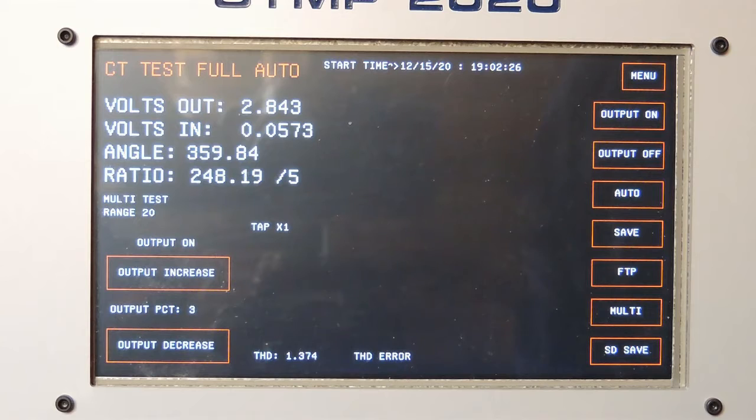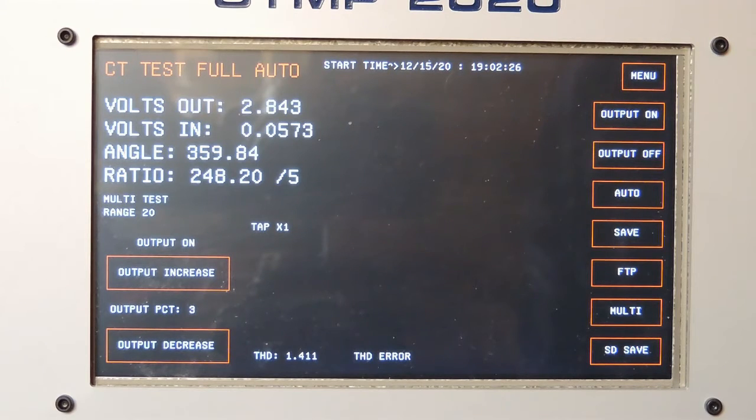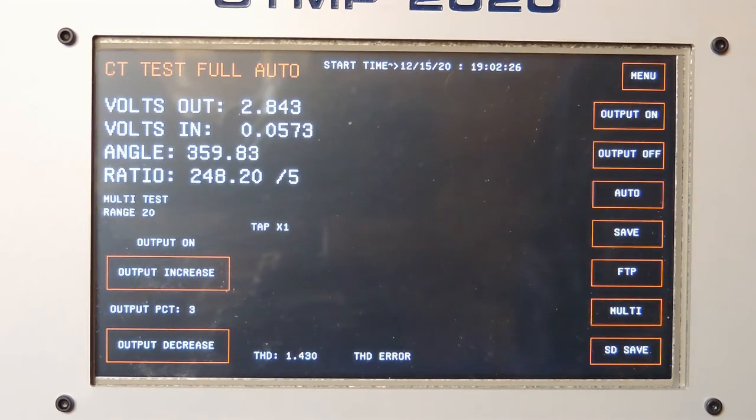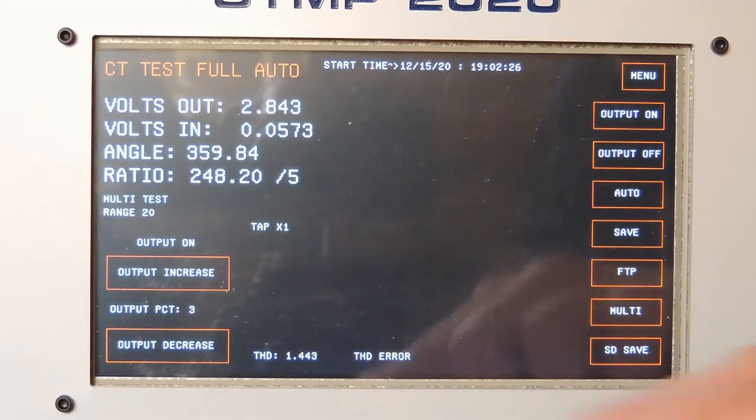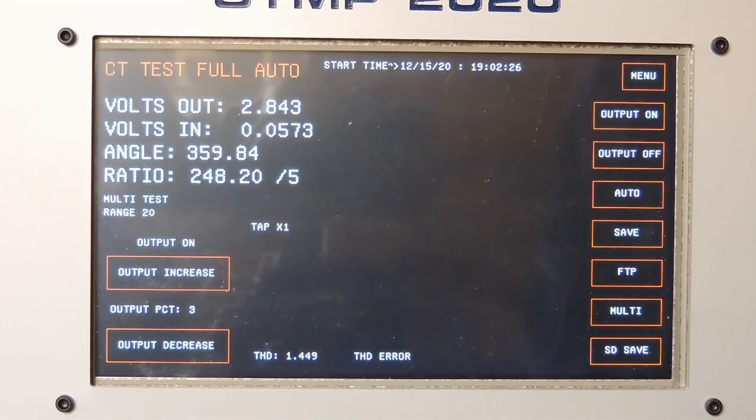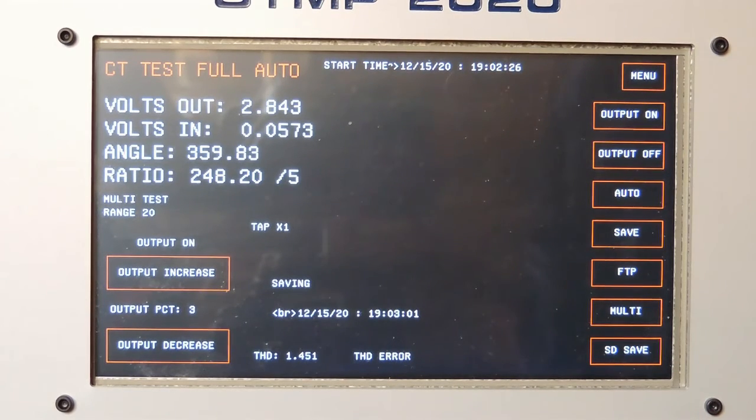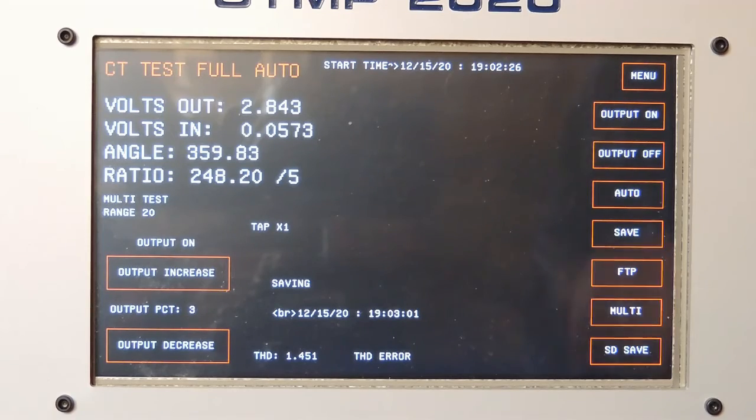Once again, it has flagged the THD error on the bottom down here. And it has stopped the ramp and gives you the best ratio it could, and it's now saving that.